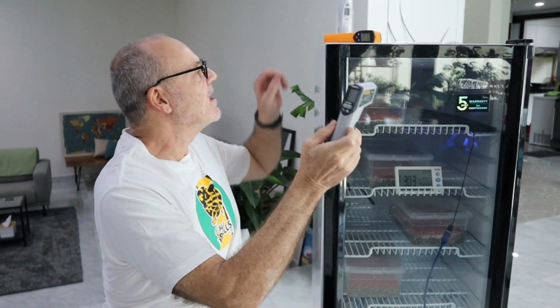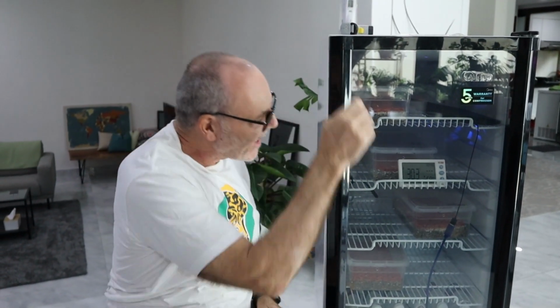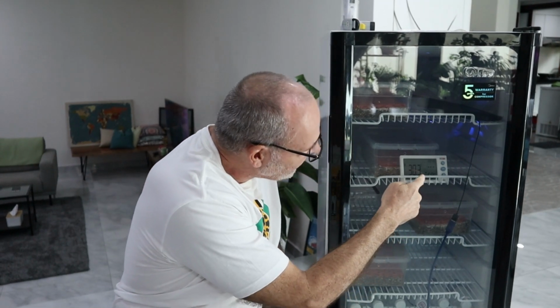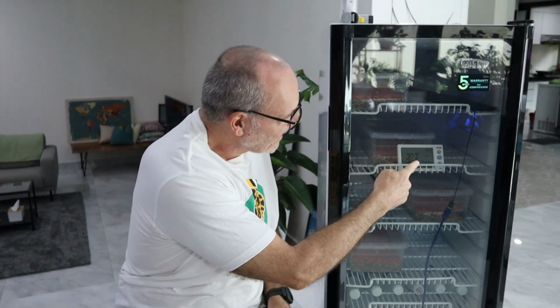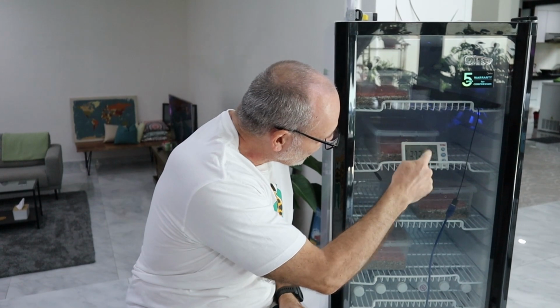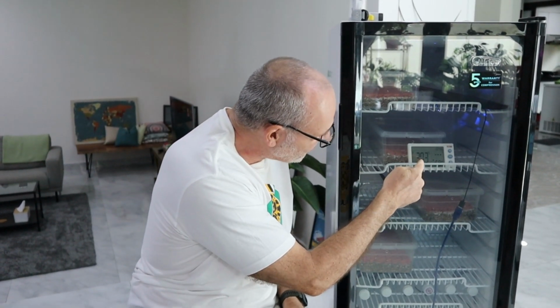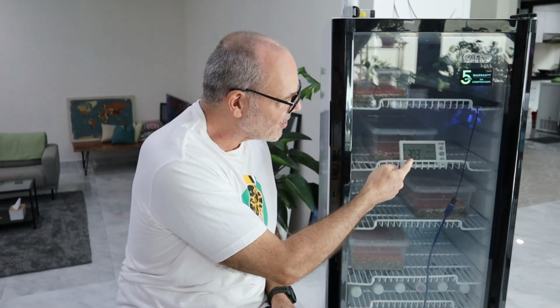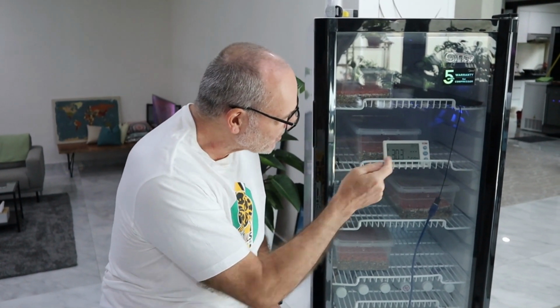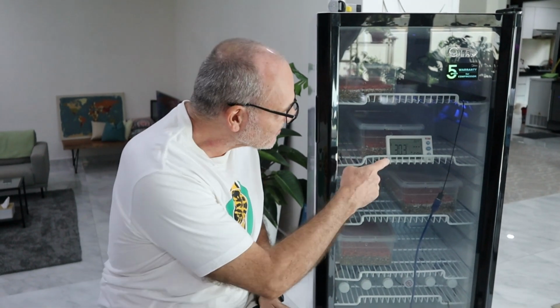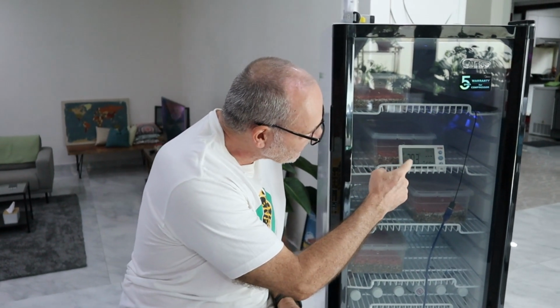So I can ignore this temperature reading here, except that I know that 30.3, 30.4 on this temperature gauge is where the incubator needs to be. So whilst it's not giving me an accurate absolute reading, it is going to give me an idea of when the incubator is too warm. So I can still use this, but I have to recognize it's not very accurate.